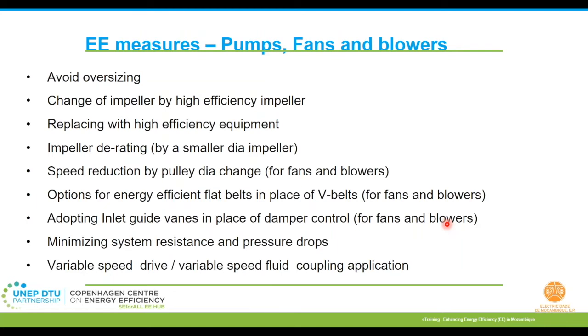For fans, pumps, and blowers, generally the most important and striking thing that I would see is oversizing, because it is one of the common mistakes everyone tends to make. Basically, you can identify if your system is oversized by checking if, let's say, the control valves are highly throttled, or you have excessive noise coming up, or there are regular maintenance issues, or there is heavy bypassing happening for the water or air.